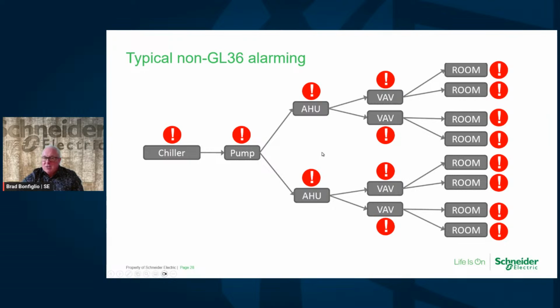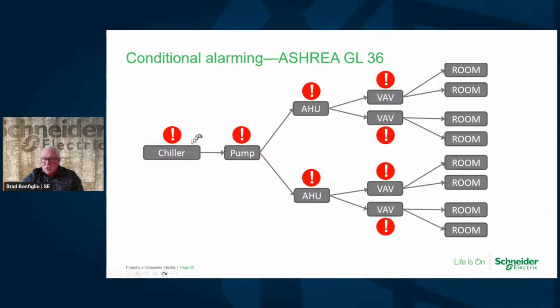So let's look at what Guideline 36 does. It's called conditional alarming. In the same scenario, it knows when you had a chiller failure. It still reports the alarms on the rooms, but it doesn't have them on the main screen. It'll still record them, but you won't get the main alarm. They'll be shunted, because it knows that the rooms, the air handlers, and the VAVs are affected and your root cause was the chiller. So I'm only going to send you the main alarm from the chiller, because it's going to cascade the conditional alarming across your portfolio.